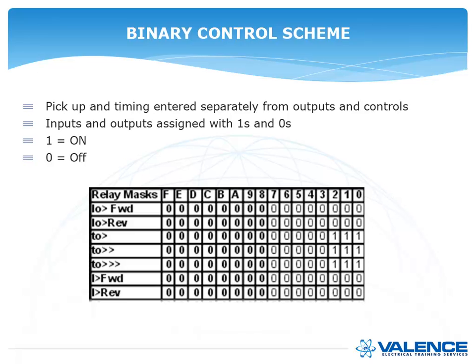So this is probably from a KCGG or an Alstom relay. And you can see that in the third row down or fourth row down where it says TO greater than, that means basically 51 in North American terms. And if you look down, if that element operates, then relays 0, 1, and 2 will all operate. And the same thing for the instantaneous overcurrent and then the second instantaneous overcurrent, because those are the only three rows that have 1s in them. The 0s means don't do anything.